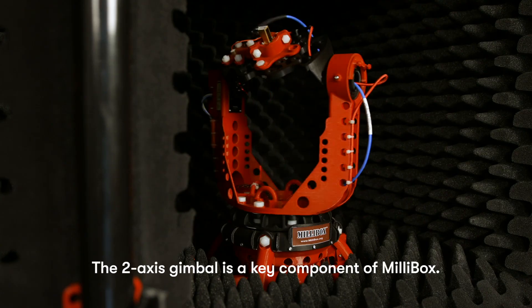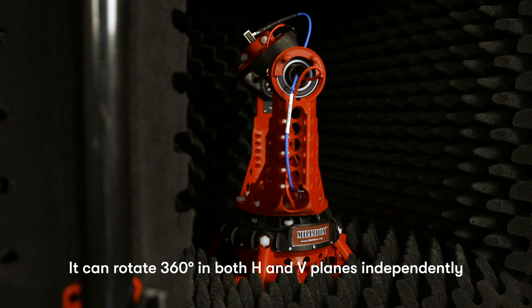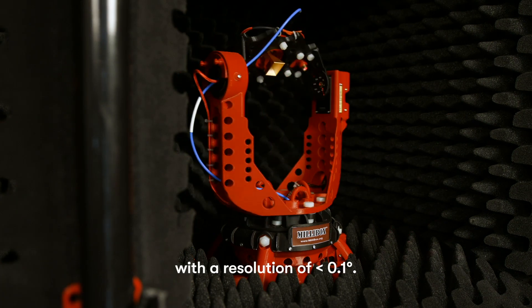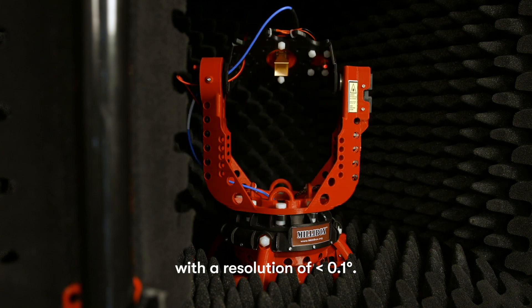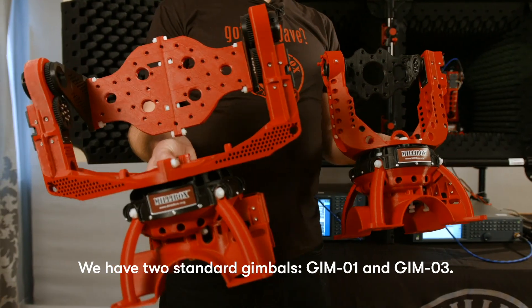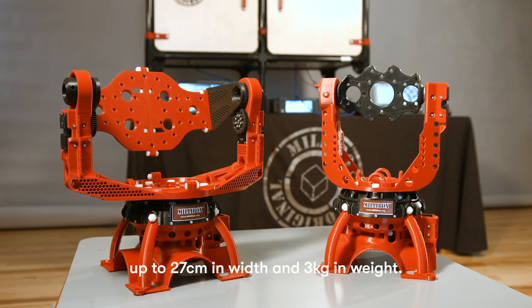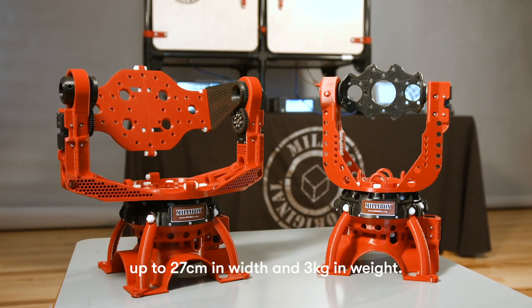The two-axis gimbal is a key component of MilliBox. It can rotate 360 degrees in both H and V planes independently, with a resolution of less than 0.1 degree. We have two standard gimbals, Gimbal 1 and Gimbal 3. The main difference is Gimbal 3 can accommodate a larger load up to 27 centimeters in width and 3 kilograms in weight.